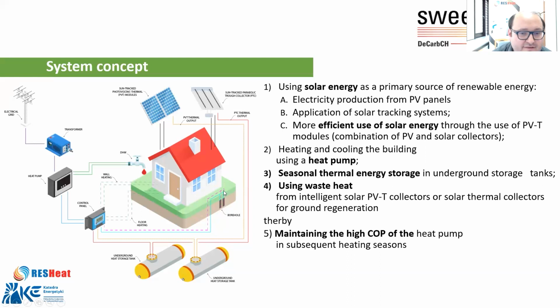This allows us to supply heat to the heat pump at the highest possible temperature. We can select one of those tanks or the boreholes to get, for example, 15 or 20 centigrades at the source side of the heat pump, allowing a high heat pump COP, so less electrical energy is needed to power it.